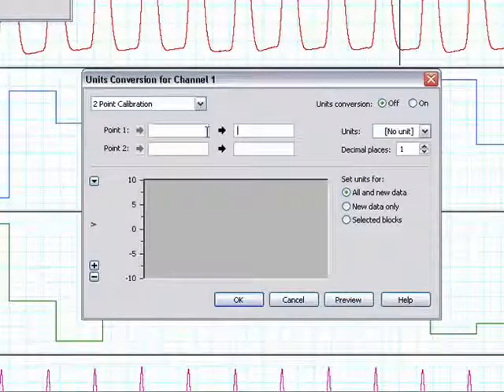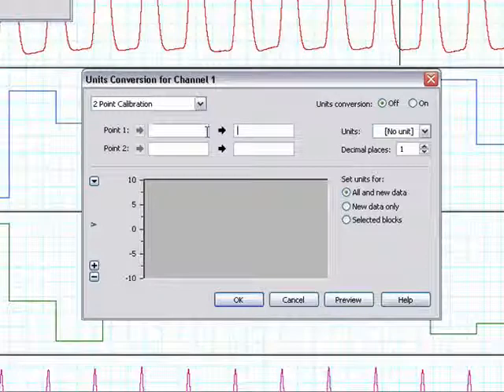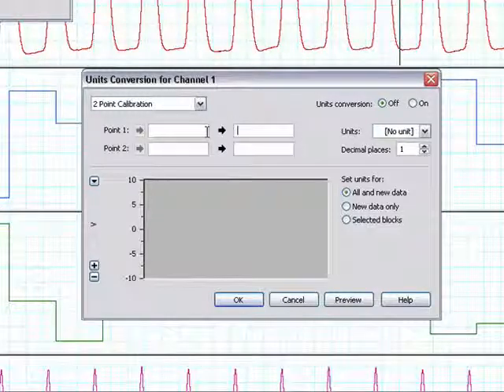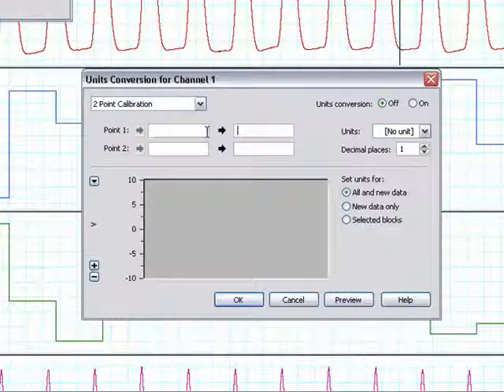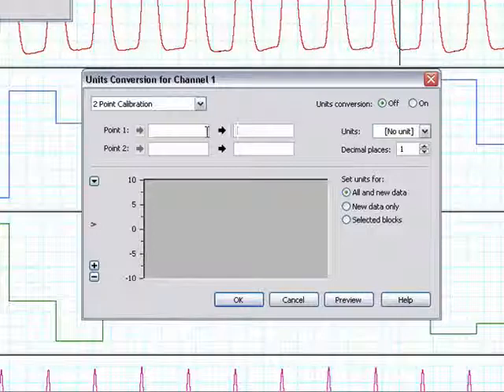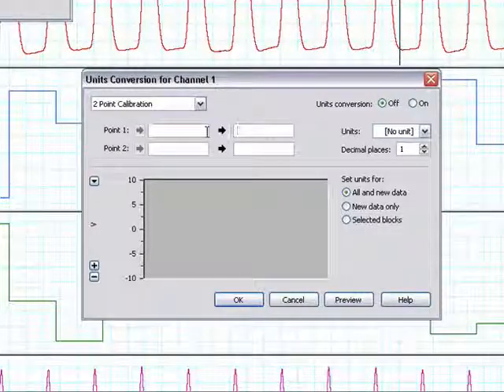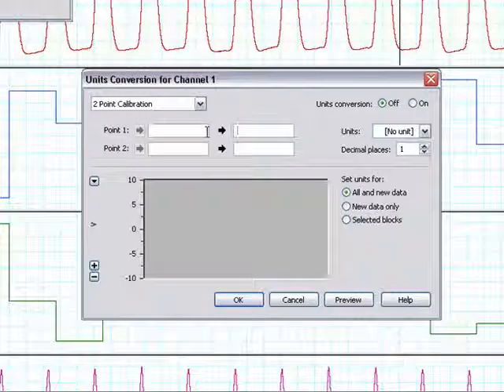For example, if you are using a temperature transducer and calibration shows that a temperature of 10 degrees Celsius gives a reading of 1 volt, and 30 degrees Celsius gives a reading of 3 volts, then you may use the two-point calibration mode to key in those values.